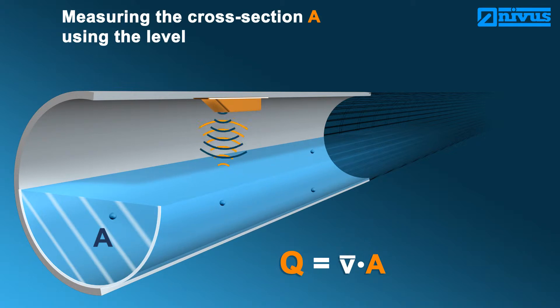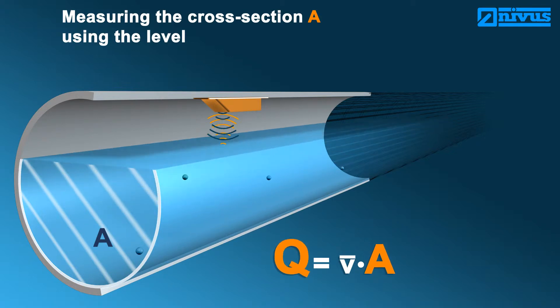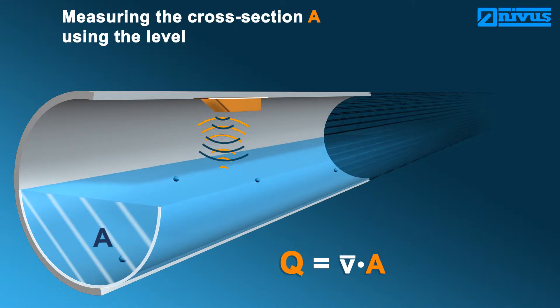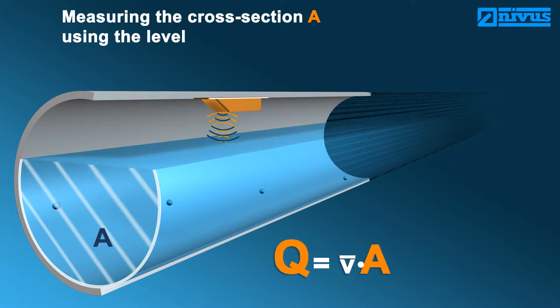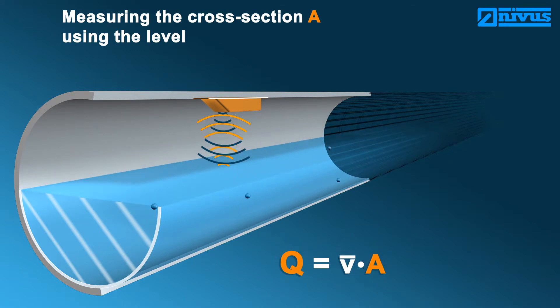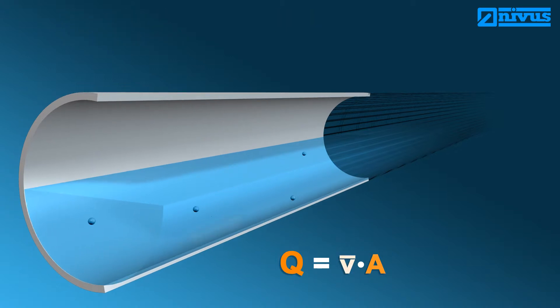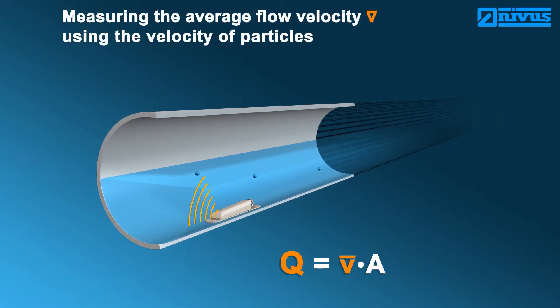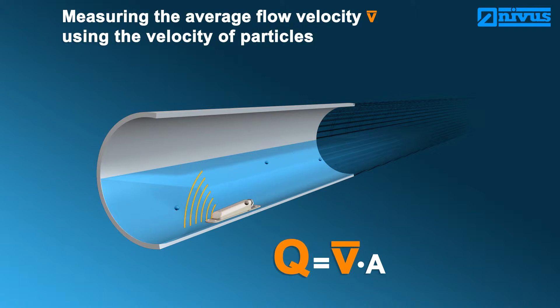If the level changes, the flow cross-section will change accordingly, and hence flow will change as well. The flow velocity is detected by measuring the particle velocity. Most media, particularly wastewater, contain dirt particles or gas bubbles moving with the same velocity as the medium. The velocity of the particles is measured using ultrasound. As soon as the velocity changes, the flow normally changes as well.